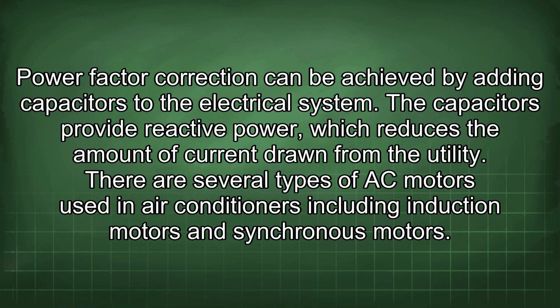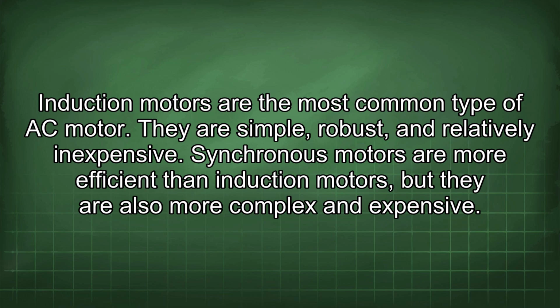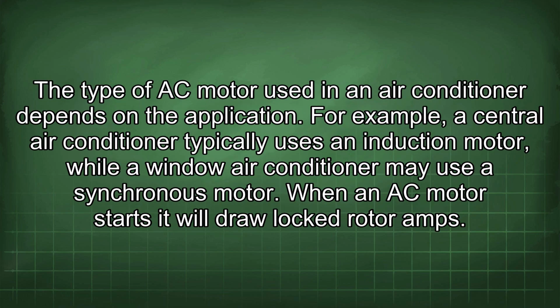There are several types of AC motors used in air conditioners, including induction motors and synchronous motors. Induction motors are the most common type of AC motor. They are simple, robust, and relatively inexpensive. Synchronous motors are more efficient than induction motors, but they are also more complex and expensive. The type of AC motor used in an air conditioner depends on the application. For example, a central air conditioner typically uses an induction motor, while a window air conditioner may use a synchronous motor. When an AC motor starts, it will draw locked rotor amps.